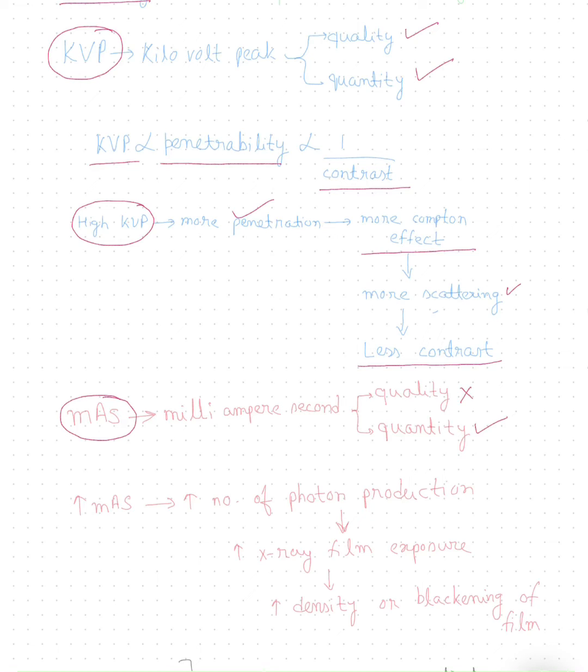When we increase the milliampere, it leads to an increase in the number of X-ray photons produced. This increased X-ray photon production leads to increased exposure of the X-ray film and increases the density of the X-ray film, meaning more blackening of the X-ray film.